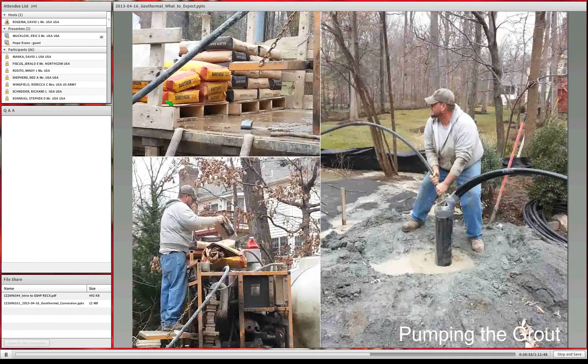The three tubes you see here are the supply and return essentially for the coil, for the loop. This tube right here is one they put down for the grout filling process. They attach a fitting to it, which connects to a pump truck that pumps the grout. As they pump the grout, filling up that hole that's 300 feet deep, they back out that tubing, as you can see them doing here. The grout is a mixture of a bentonite-based grout as well as silica sand.